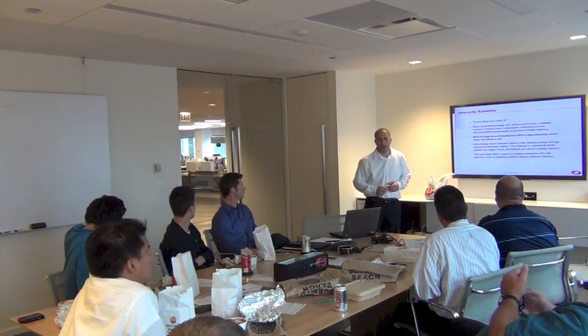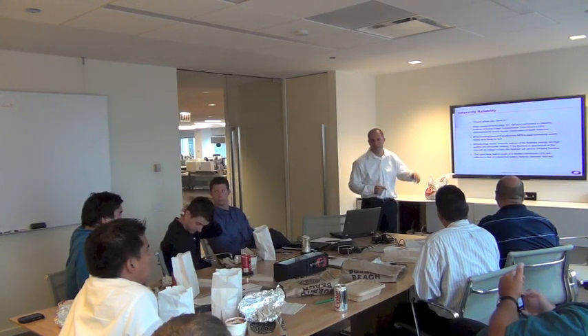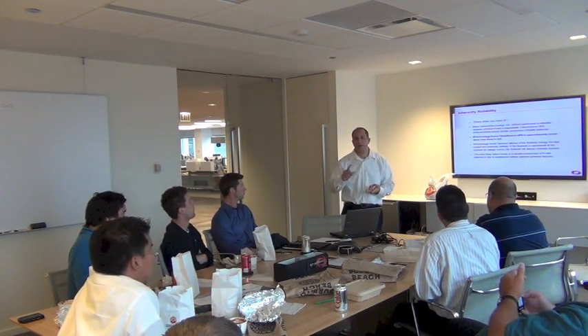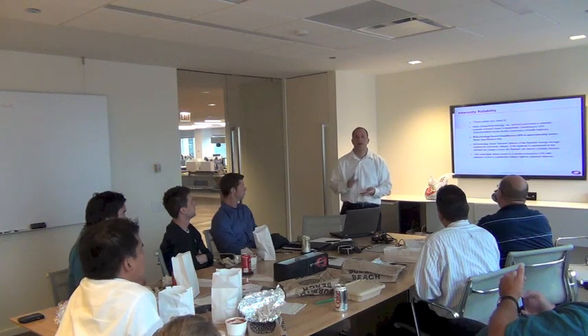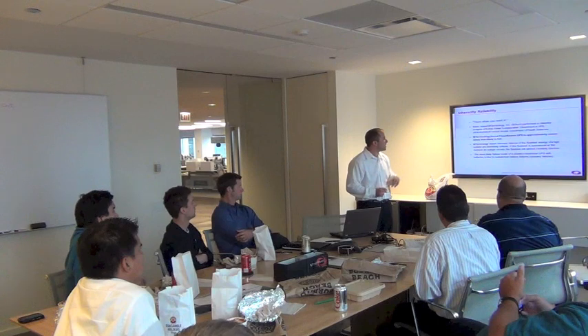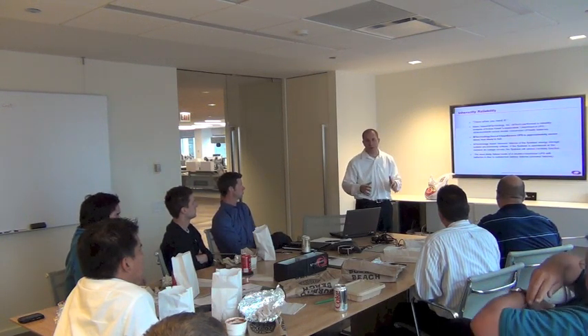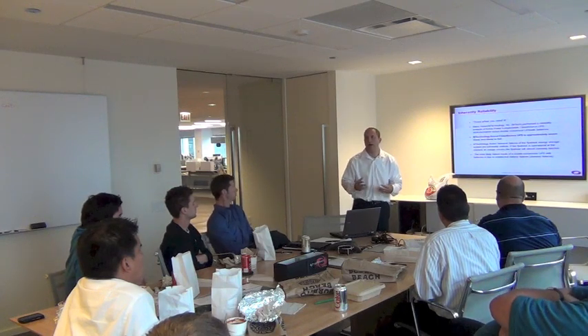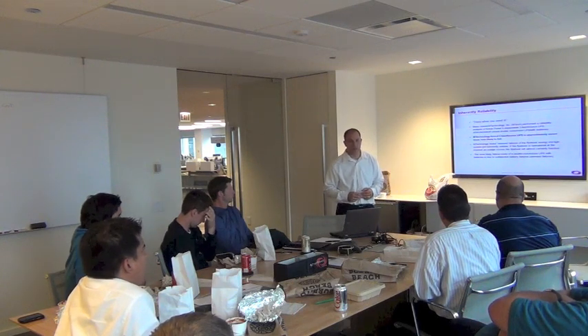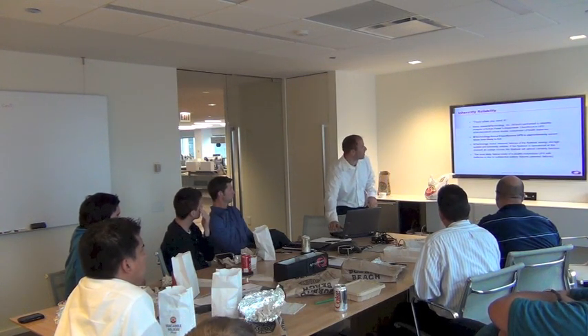So this is Massachusetts-based M Technologies. Are you guys familiar with M Technologies? Have you heard of them? They do a lot of reliability studies for a lot of people in the industry. They've done it for us, done it for Cisco, EYP, Uptime Institute. They have a lot of different customers out there. And they actually did a study on our CleanSource UPS versus traditional battery-based UPS with VRLA batteries. What they found was it was 7 times less likely to fail in the event of an outage. And it really came down to demand failures between batteries and mechanical energy storage. Interesting study. So I'm going to fly through a lot of these marketing slides.